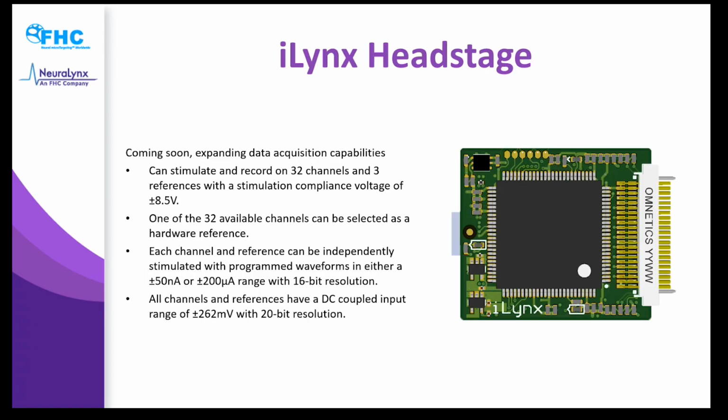So this is the new iLynx head stage. This is a prototype picture of it. But it will be able to stimulate and record on 32 channels with 3 references and a stimulation compliance voltage of plus or minus 8.5 volts. And then one of the 32 available channels can also be selected as a hardware reference. And then each channel can be independently stimulated with programmed waveforms in either plus or minus 50 nanoamps or plus or minus 200 microamps with a range of 16-bit resolution.